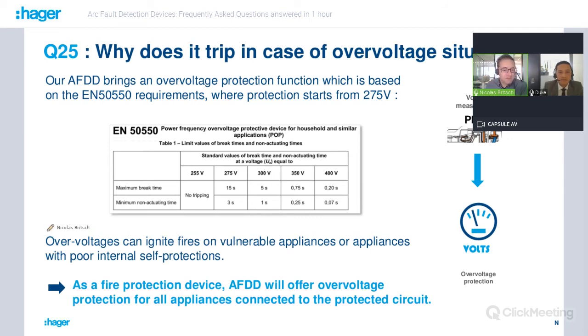But why do we have an overvoltage protection? Because overvoltages can ignite fires on vulnerable appliances or appliances with poor internal self-protections. And as a fire protection device, AFDD will offer overvoltage protection for all appliances connected to the protected circuit. So that's the reason why we also embed this kind of protection.